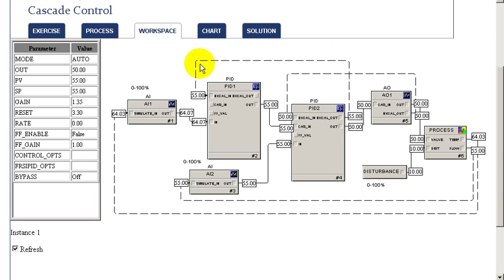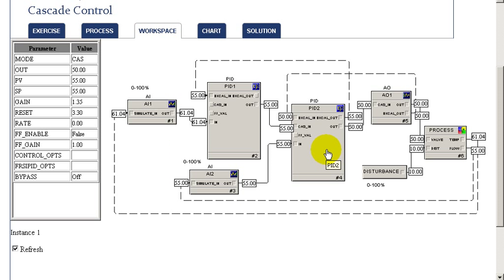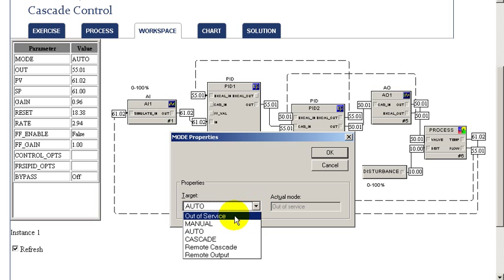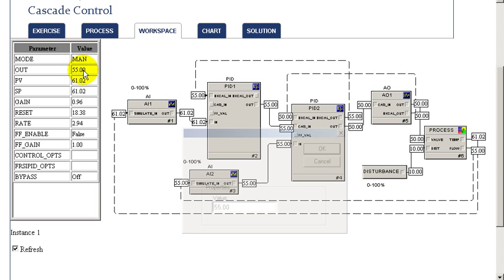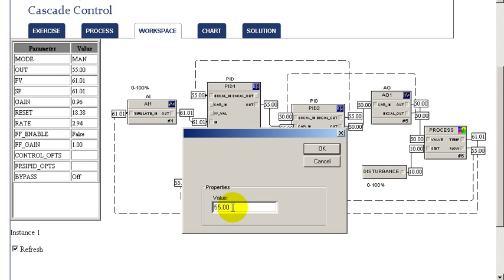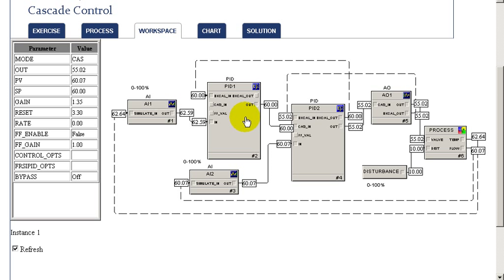Under this condition of the loop being in auto, the back-cal is used by the master loop to set its output to follow along. We can then change the slave loop to cascade mode — now its setpoint is determined by the master loop. Putting the master into manual temporarily, we change the output of our master loop by a step, and we notice that change is immediately reflected as the setpoint to our slave loop. The output of our master loop becomes the setpoint of our slave.